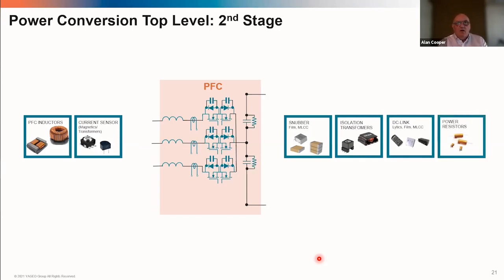So what the power factor correction does is the inductor basically takes the reactive elements of this particular stage and tries to neutralize them, so that the power factor itself is close to 1. That allows you to transfer real energy to the output, and neutralize the effect of energy bouncing back between the reactive components.